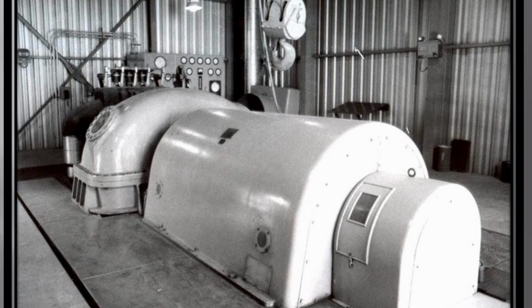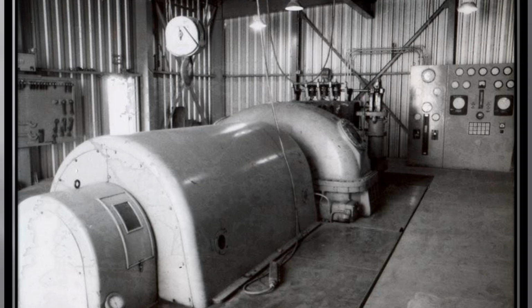Installation of the turbine generator and related equipment progressed after the steam turbine was reconditioned. The generator will produce up to 6 megawatts of electricity at 13,800 volts, operating in synchrony with the Southern California Edison system.